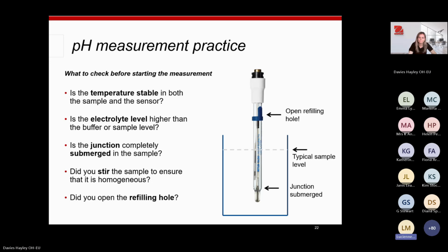On the maintenance sheet, it says to soak a dried electrode in distilled water. No, we would not ever recommend soaking in distilled water. That's a no-no. The solutions that you're soaking in need to be ion rich. They need to have lots of those H+ ions to keep the gel layer nice and hydrated. Thanks, Hayley.